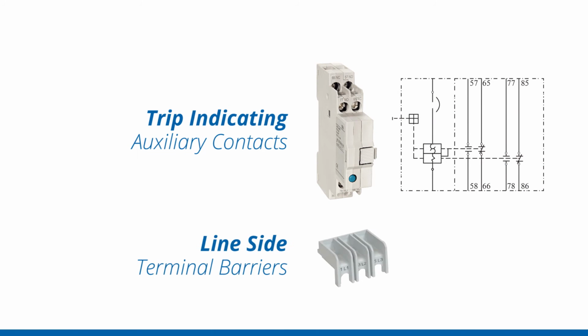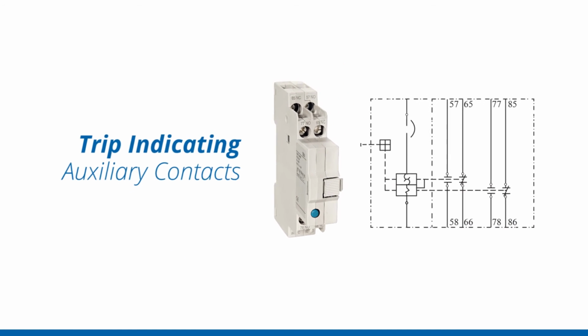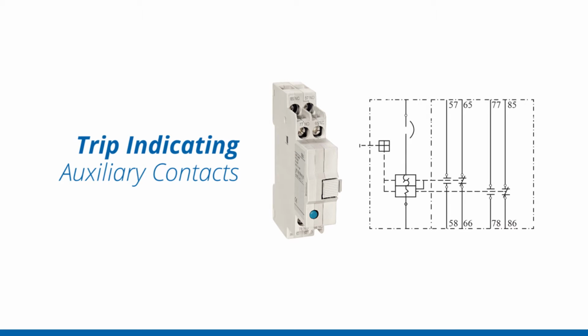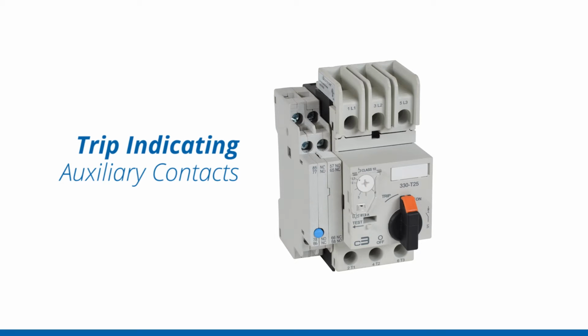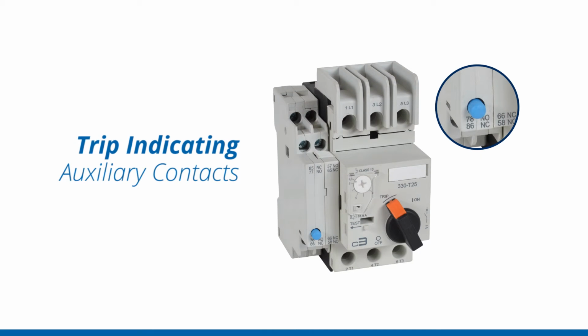Two elements that are primarily new to this assembly would be things like trip indicating auxiliary contacts and line side terminal barrier. Trip indicating auxiliary contacts ensure that the device can provide indication of whether an overload or a short circuit has occurred. In this example, there are 4 contacts available. 2 contacts are associated with overload, meaning that if there was a thermal overload trip, those contacts would change state. If it's a magnetic short circuit, then all 4 would open and the blue button on the front would protrude, providing the required visual indication of what type of fault occurred.